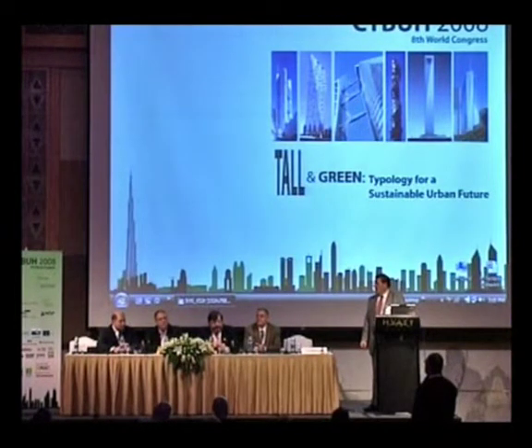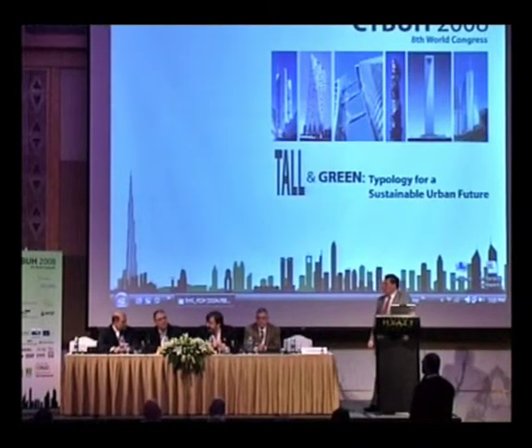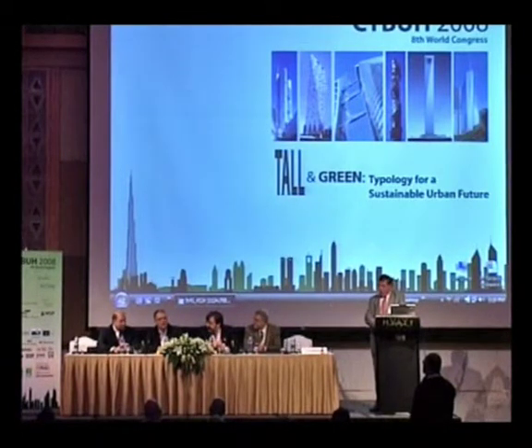One of the problems we have, particularly in the UK with our own pressurization code, is that the amount of design information and certainty you need about the building when you start building it means that when you come to test the building, often pressurization systems are either massively over-designed and you get lots of other problems to do with doors opening, or they don't work at all, they fail completely. I've been to building tests where the pressure was supposed to achieve 50 pascals and it achieved 2.5 in a test, for example.